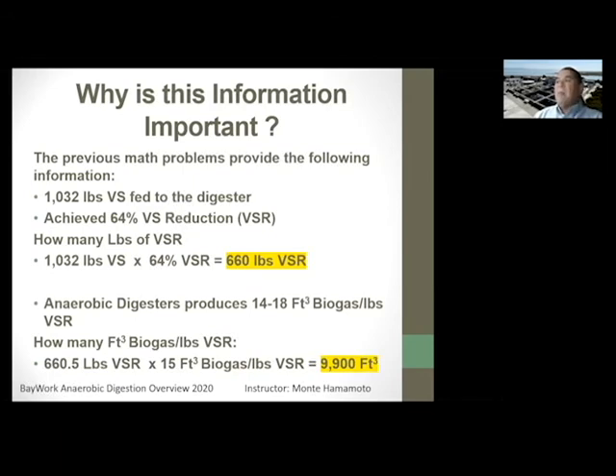Why is that number important? If you look at gas production, we produce 14 to 18 cubic feet of biogas per pound of volatile solids reduced. So how many cubic feet of biogas did we produce when we reduced the volatile solid content by 660 pounds? Taking a number in between, 15 cubic feet of biogas per pound reduced, we produced 9,900 cubic feet of biogas.